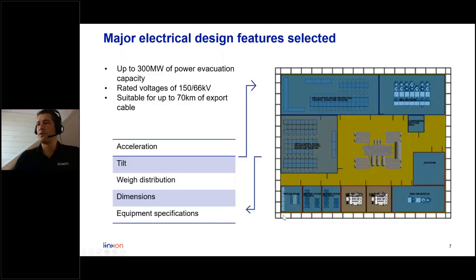So this is the solution we've presented, and it's very challenging to cover in 10-15 minutes the whole process that went into selecting this concept. We've arrived at a solution around 300 megawatts, with rated voltages of 150 kilovolts for export cables, 66 kilovolts for array cables, suitable up to 70 kilometers for export cable.